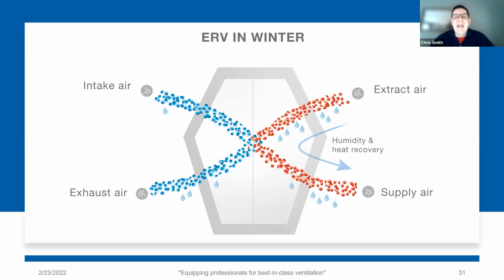Now, an ERV adds the ability to transfer humidity as well as heat. So now let's look at the ERV in winter. Again, in winter, our indoors is typically more humid than our outdoors. The ERV is able to transfer heat between the air streams, but it's also able to take some of the indoor humidity and retain some of that for comfort. Now, if designed properly, the ventilation rate will be sufficient that we won't retain too much humidity in the winter. You notice that the exhaust air still is carrying some of the humidity outdoors. But with an ERV, we're able to retain some moisture indoors along with the fresh air delivery. And so we maintain a healthier indoor environment that is able to stay relatively comfortable.